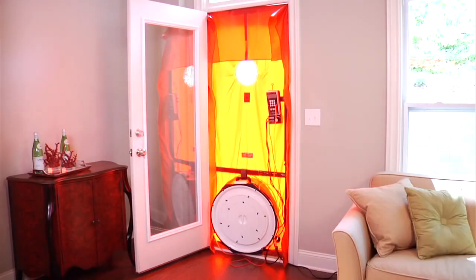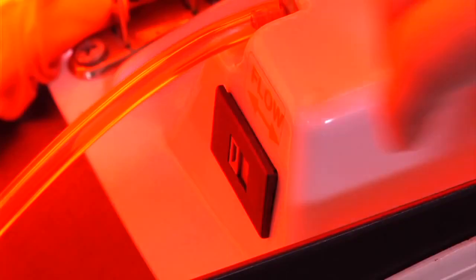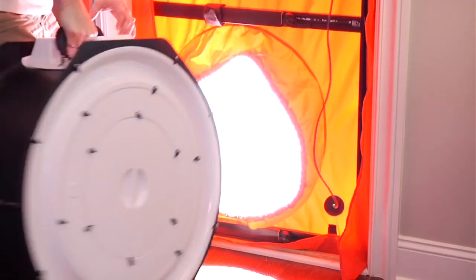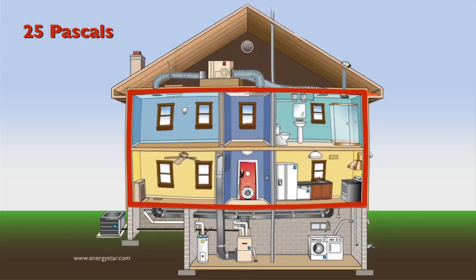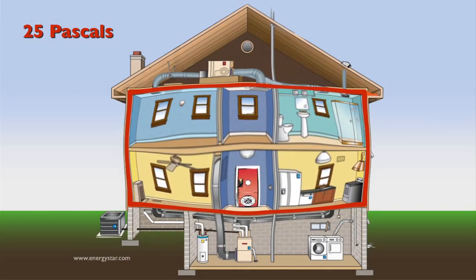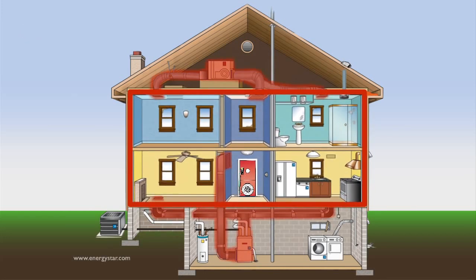Now let's measure the leakage to the outside. With the blower door in place, flip the fan flow switch, or if your fan does not have a flow reversal switch, turn the fan around and pressurize the home to 25 pascals with reference to the outside. Because the ducts are considered part of the building envelope, they should read the same pressure as the home. However, ductwork leaks, and the pressure in the duct system will usually be lower than the pressure inside the home.